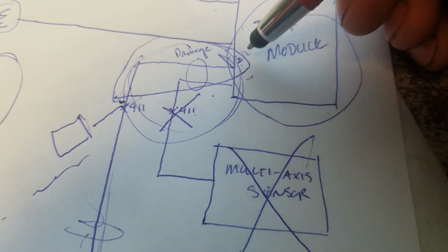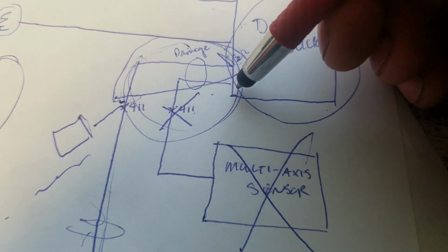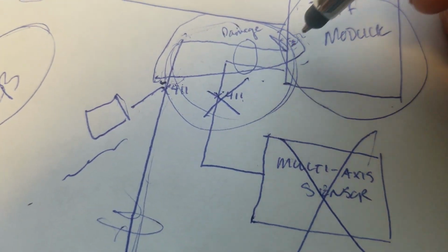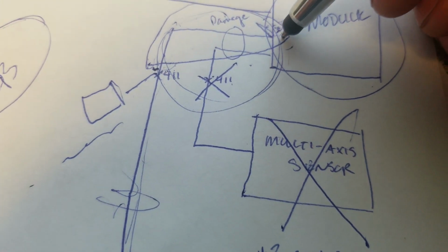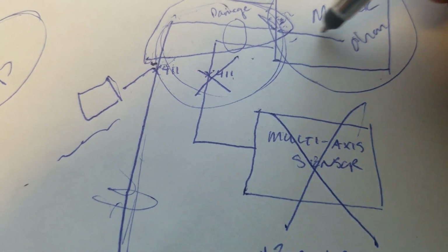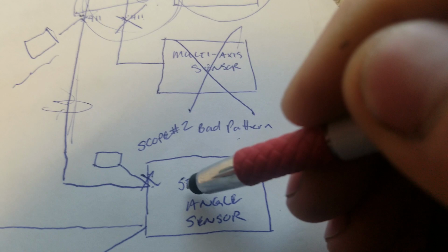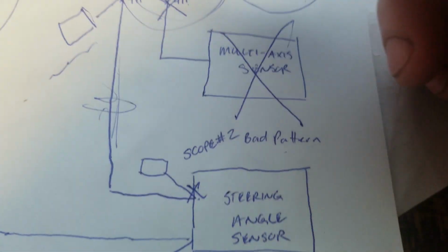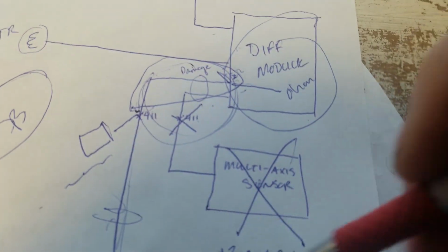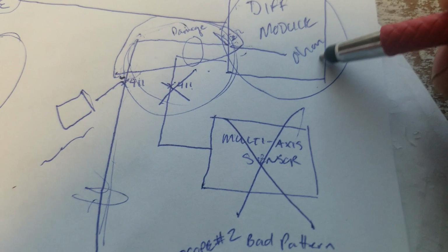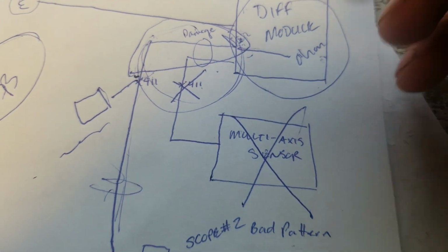Now that's going to be tough to do because we can't disconnect the connector and look at it, because we'll have no signal. So I guess what we could do is an ohms check. We could use an ohm meter here, put one lead there, and one lead here with everything disconnected and ohm out these two wires individually, right? We could do the high speed or the high line and the low line and see what we got. And we would have found our issue with an ohm meter, okay?